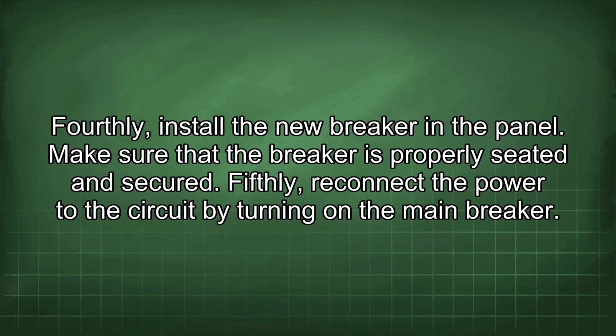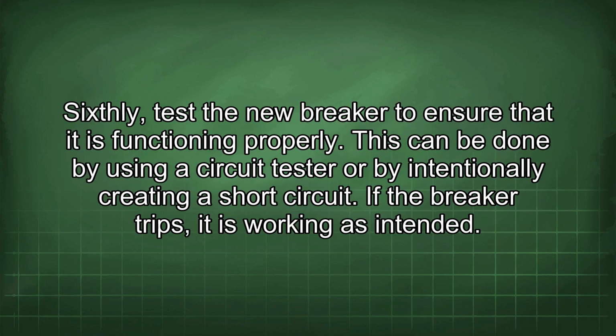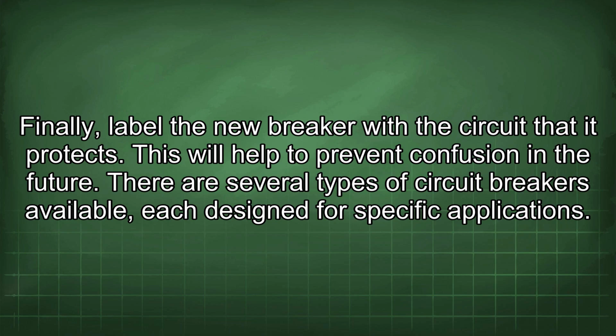Fifthly, reconnect the power to the circuit by turning on the main breaker. Sixthly, test the new breaker to ensure that it is functioning properly. This can be done by using a circuit tester or by intentionally creating a short circuit. If the breaker trips, it is working as intended. Finally, label the new breaker with the circuit that it protects. This will help to prevent confusion in the future.